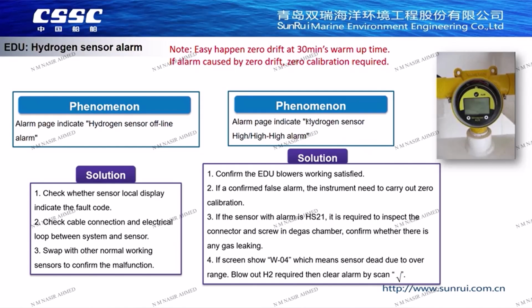Next is the continuous sensor detection alarm that cannot be reset. It is because the hydrogen sensor has contacted a high concentration of hydrogen gas, which leads to sensor crash. W04 alarm will be displayed on the local screen. To reset W04, it is necessary to manually start the EDU blower and run it for about 10 minutes to ensure that all hydrogen is cleared in the wet pipe. Then use the magnetic bar to scan the check mark on the local screen. The alarm can be reset.